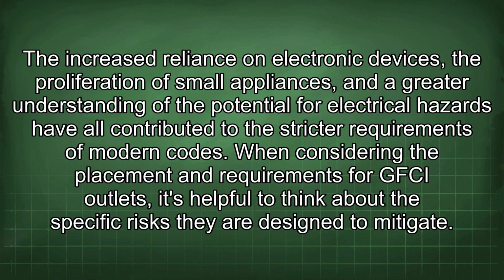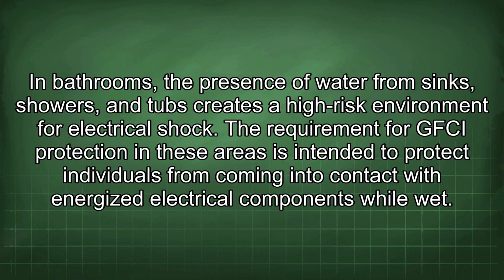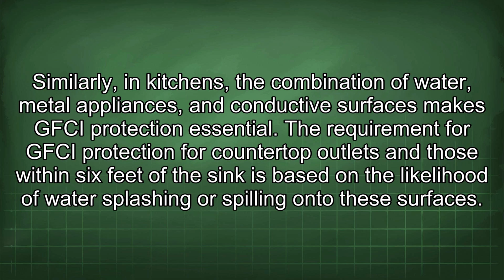When considering the placement and requirements for GFCI outlets, it's helpful to think about the specific risks they are designed to mitigate. In bathrooms, the presence of water from sinks, showers, and tubs creates a high-risk environment for electrical shock. The requirement for GFCI protection in these areas is intended to protect individuals from coming into contact with energized electrical components while wet. Similarly, in kitchens, the combination of water, metal appliances, and conductive surfaces makes GFCI protection essential. The requirement for GFCI protection for countertop outlets and those within 6 feet of the sink is based on the likelihood of water splashing or spilling onto these surfaces.